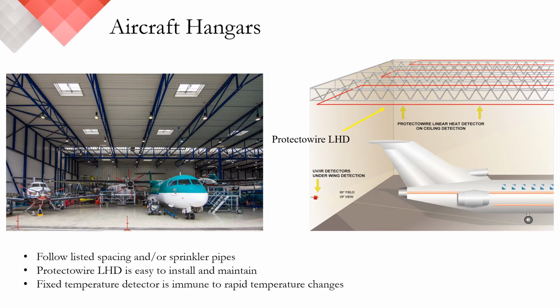Aircraft hangars are another excellent application and well suited for any of the detection devices offered, including fiber optic. Due to the volatile nature of these facilities and the various fuels and chemicals present, a foam suppression system is required. At the ceiling level, linear heat provides the pre-action to initiate the foam delivery and is more economical when commissioning and testing are considered. Imagine the number of spot detectors required in a hangar that can accommodate several commercial or passenger aircraft. Based on listed spacing and ceiling heights, the number grows into the thousands. Now, consider the process needed to maintain these individual detectors on an annual basis. Great work if you can get it, but if you're looking for a quicker, more economical solution for both your team and your customers, then you need to consider linear heat.